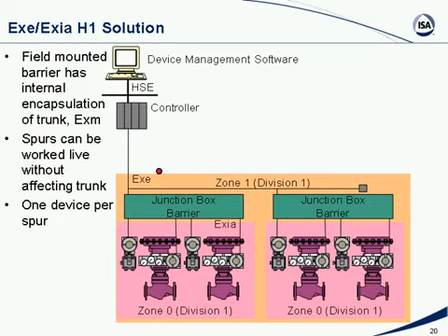Another beauty here, okay, is that I can still use redundant power supplies. Okay, I cannot have redundant safety barriers, but I can have redundant power supplies and power conditioners. Another thing, okay, is that this way I only connect one device per spur, and a lot of people feel good about that because if I create a short circuit on one of the spurs, that spur is current limited so that it doesn't affect the other devices on this bus. Okay, it only affects that one device. So it's an availability issue also. So this solution solves quite a lot of things, in fact.